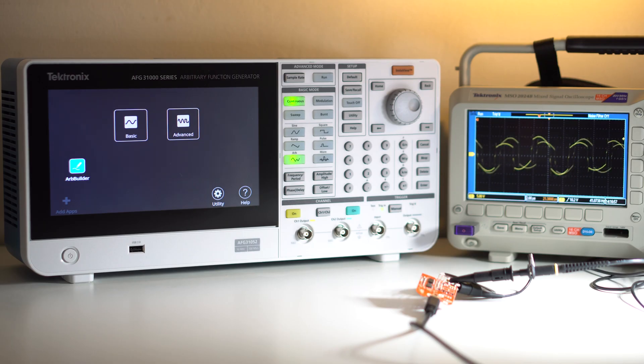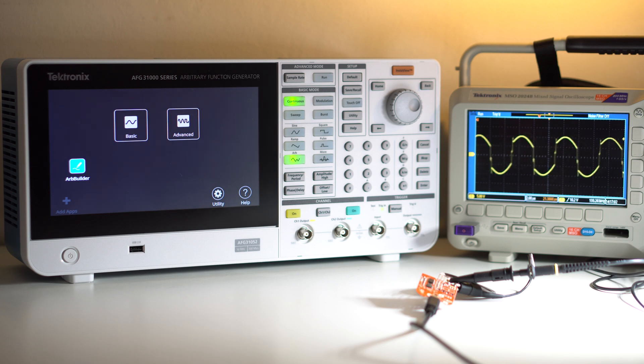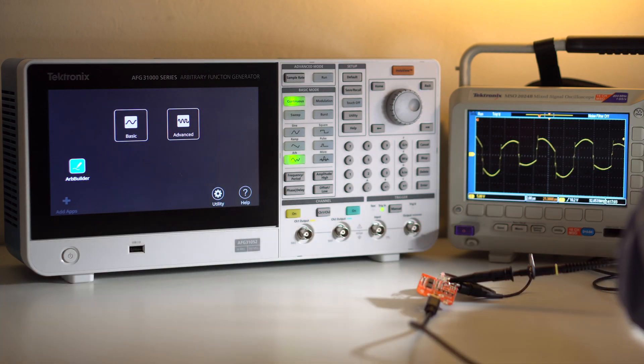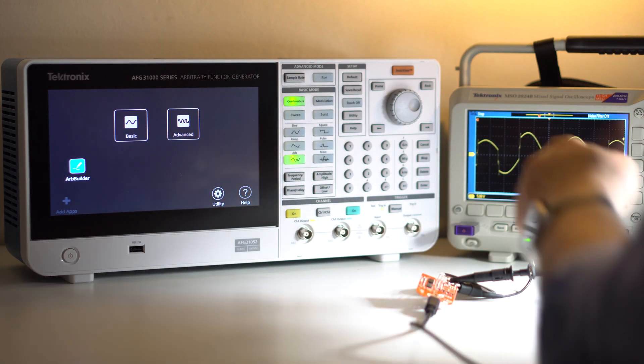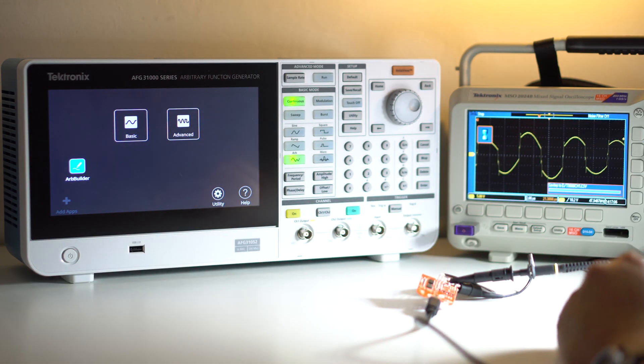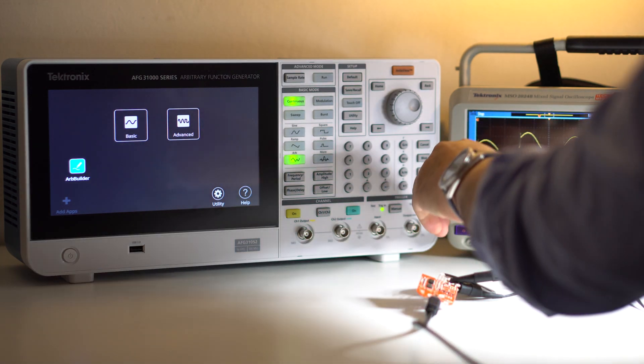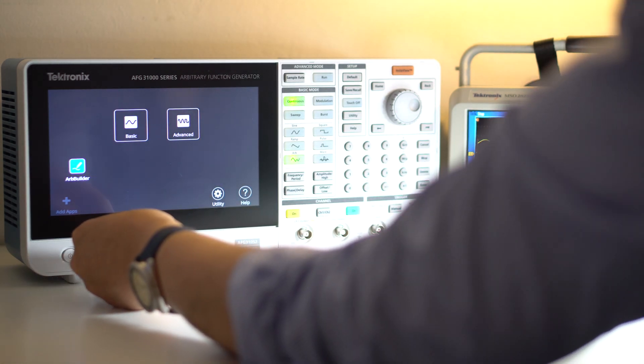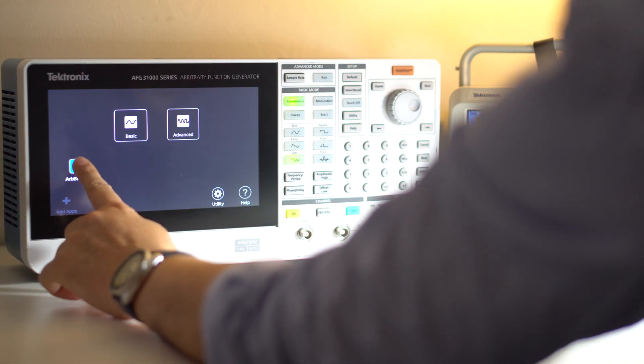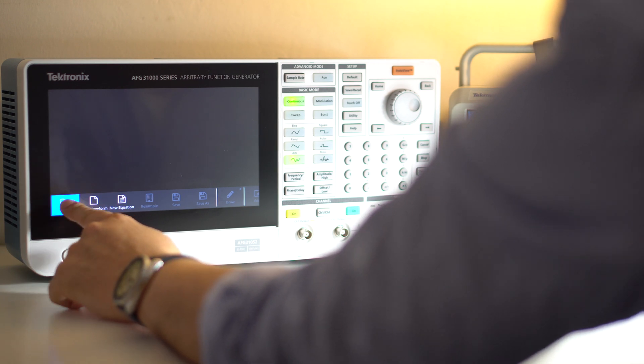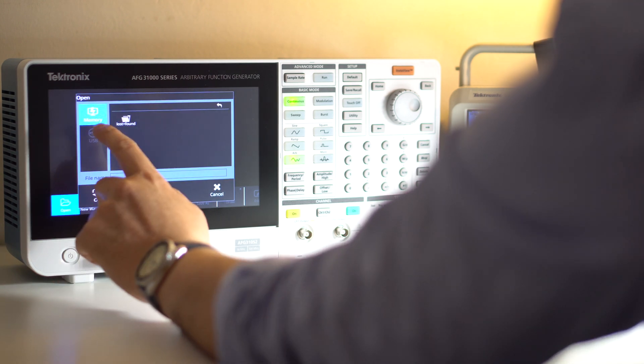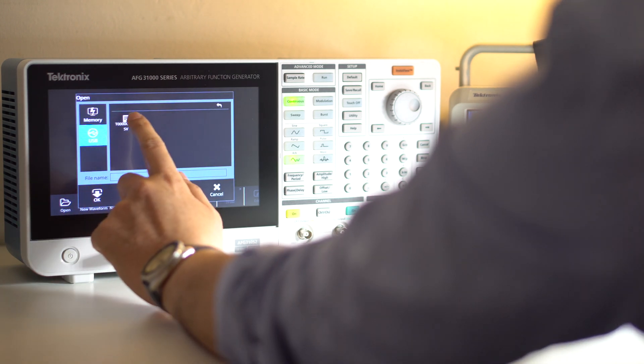In terms of arbitrary waveform file creation, there are many other ways to do that. One method, which I think will work with any Tektronix scope from the past decade at least, is to just copy the desired signal from the scope, then insert the USB memory key into the AFG31K, and then open it using the ArbBuilder application. You can then drag cursors and cut to the desired portion of the trace that you want to play out.